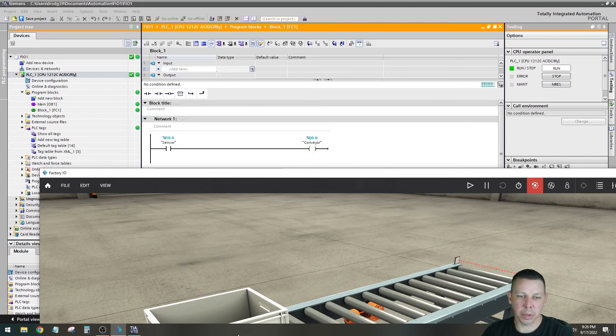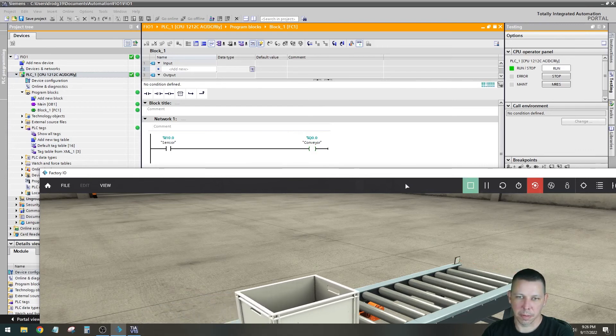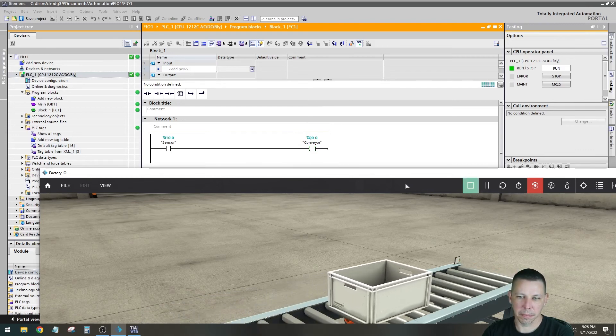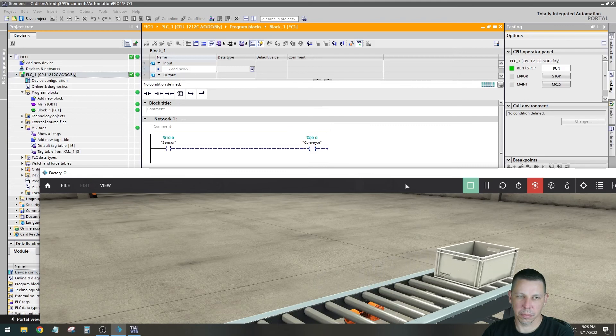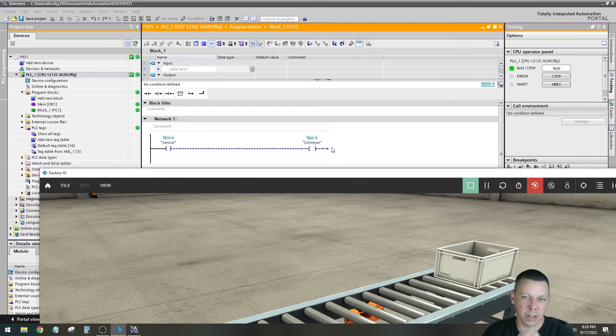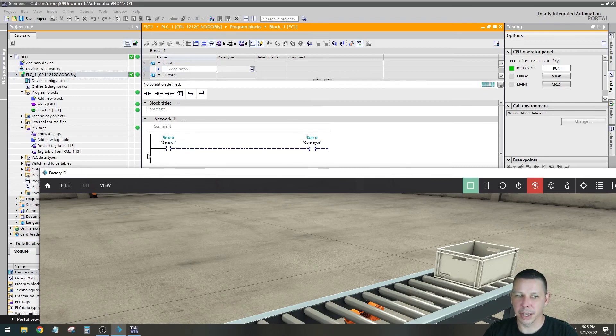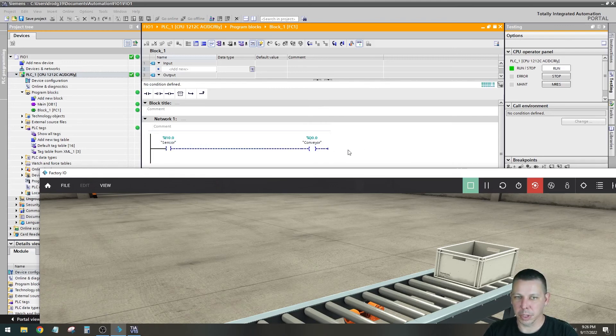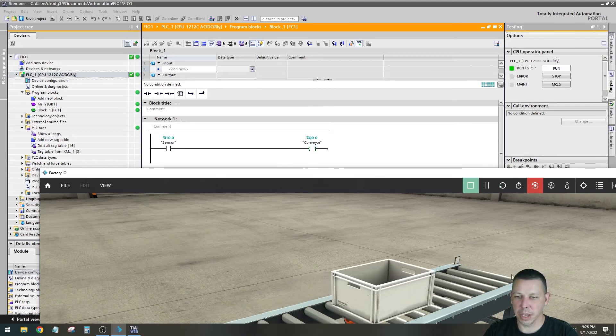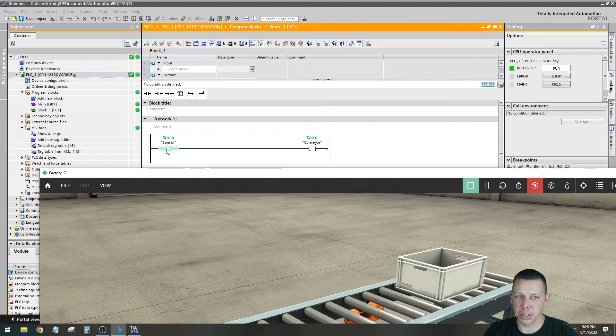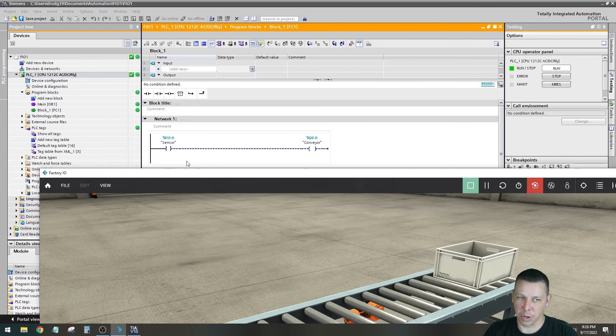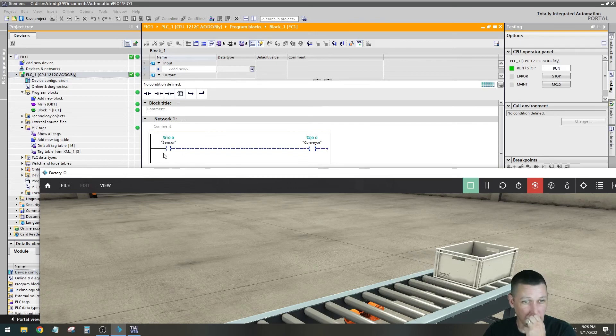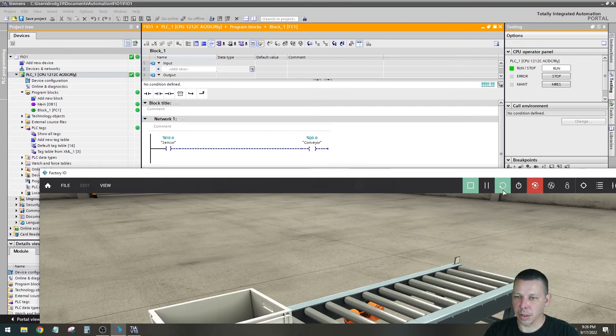I think we're going to be able to see this thing go and see the sensor change at the same time. There it went. So you see the sensor drop out. I didn't get to find a good example of it last time, how you can see when it's green the whole way across, you know, that it's true instead of just a highlighted little box. It shows you the full path of where the signal is being stopped basically. So you can hit the restart button there and it'll play again. So the conveyor is made until this changes state. And when that changes state, that goes to input 10 in the processor and it drops that output out, which is controlling the conveyor motor.